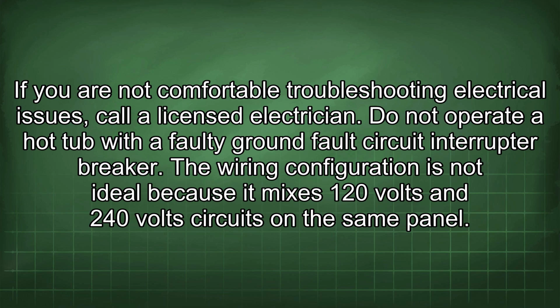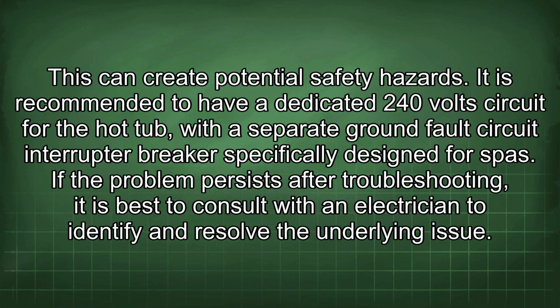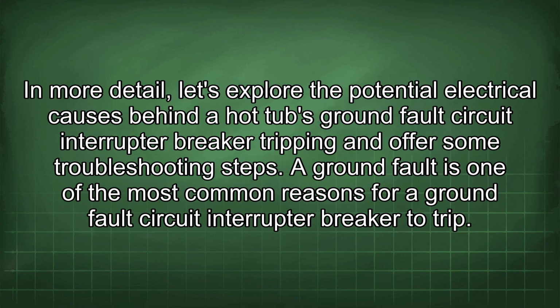The wiring configuration is not ideal because it mixes 120 volt and 240 volt circuits on the same panel. This can create potential safety hazards. It is recommended to have a dedicated 240 volt circuit for the hot tub with a separate ground fault circuit interrupter breaker specifically designed for spas. If the problem persists after troubleshooting, it is best to consult with an electrician to identify and resolve the underlying issue. In more detail, let's explore the potential electrical causes behind a hot tub's ground fault circuit interrupter breaker tripping and offer some troubleshooting steps.